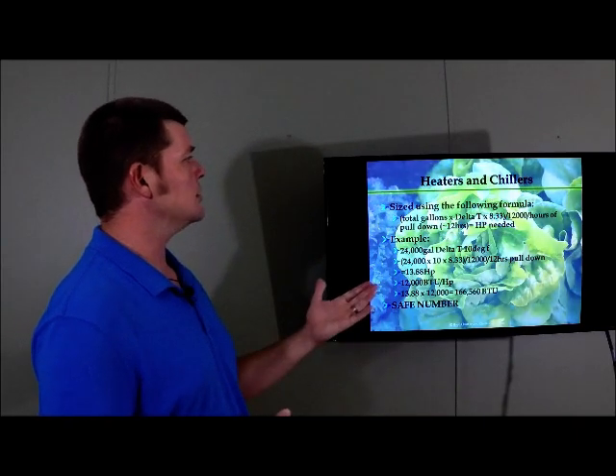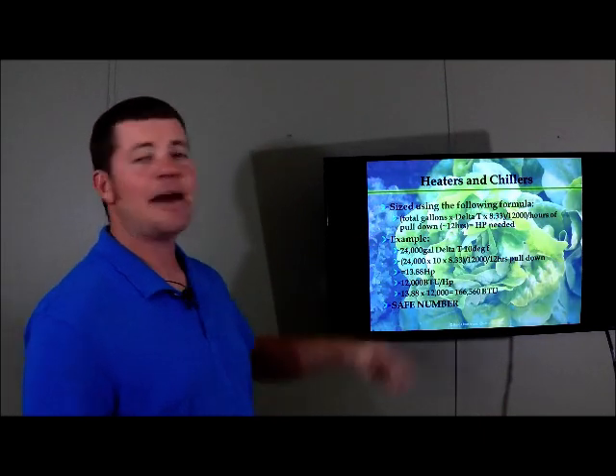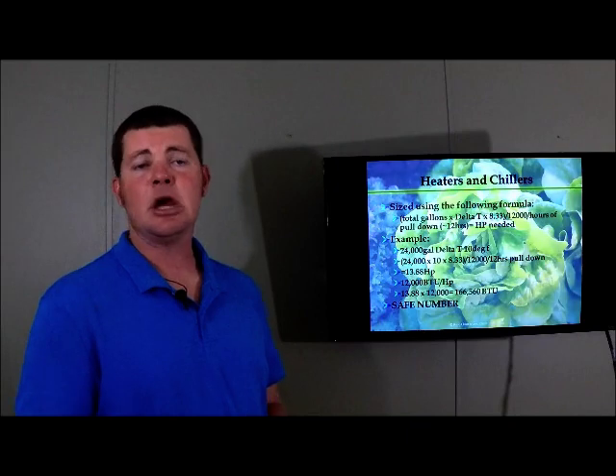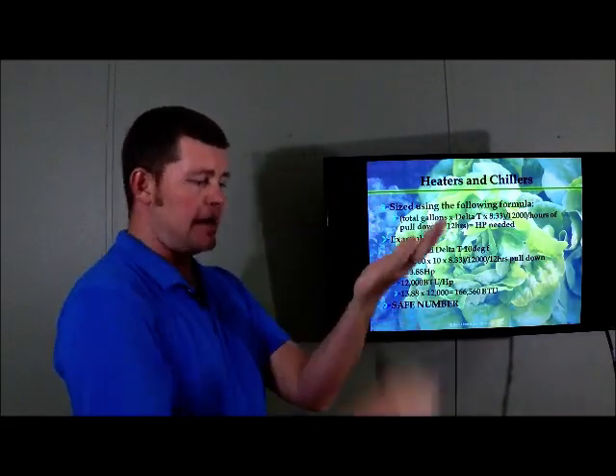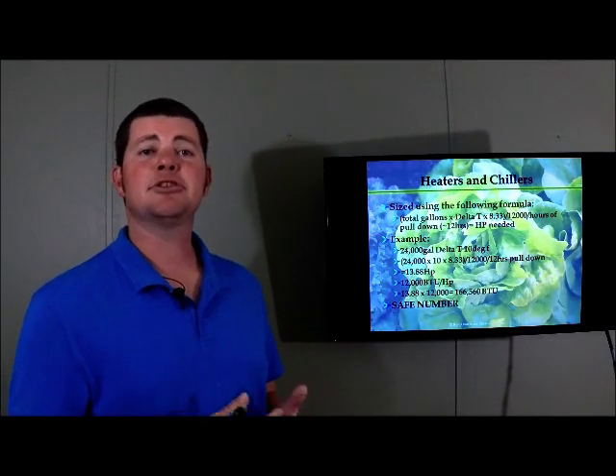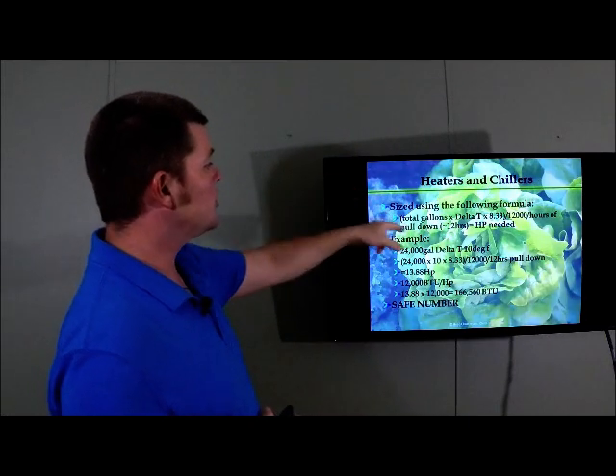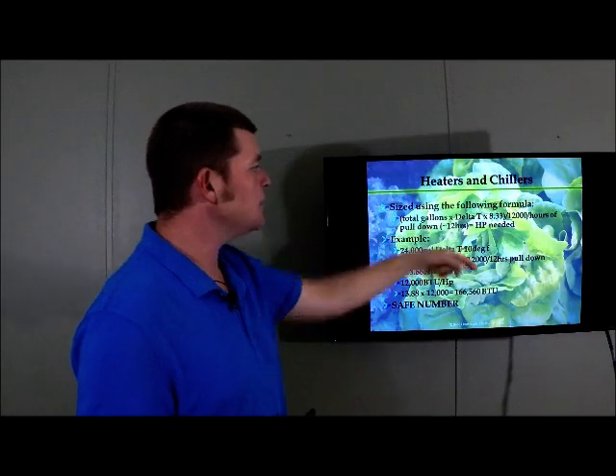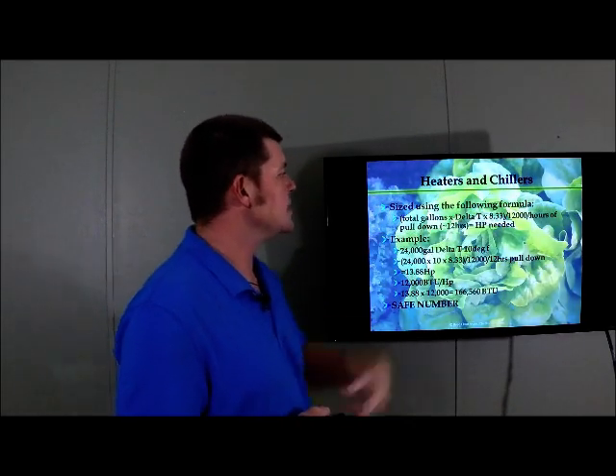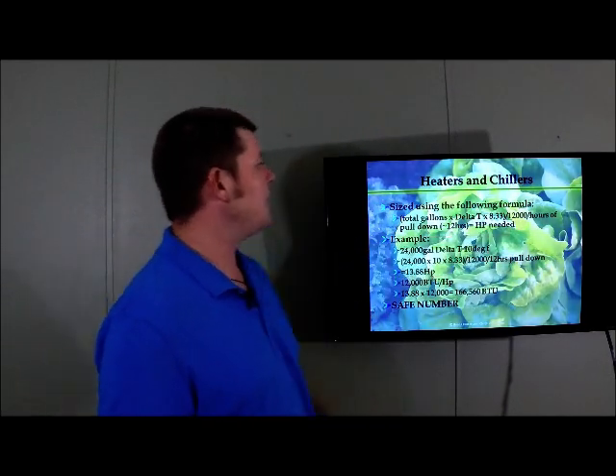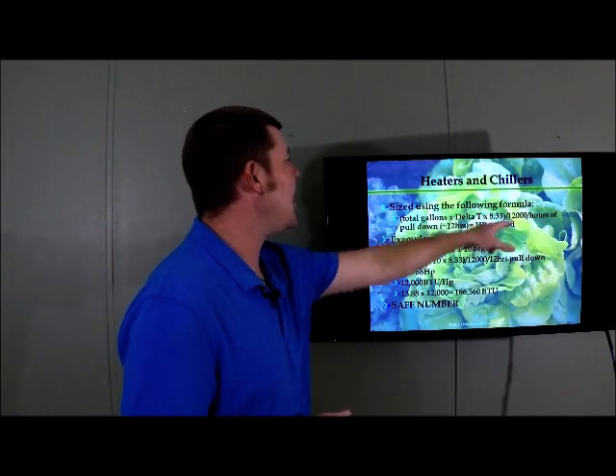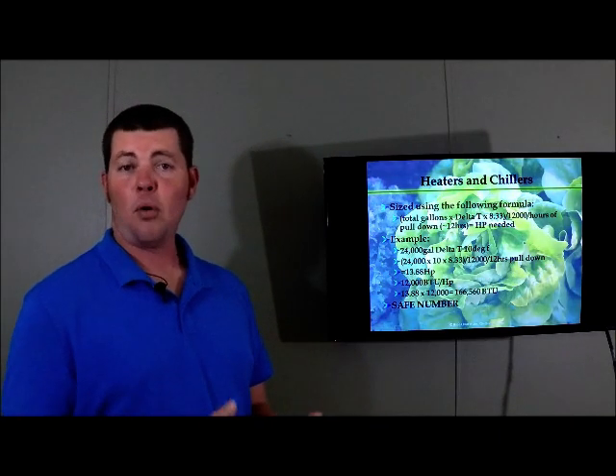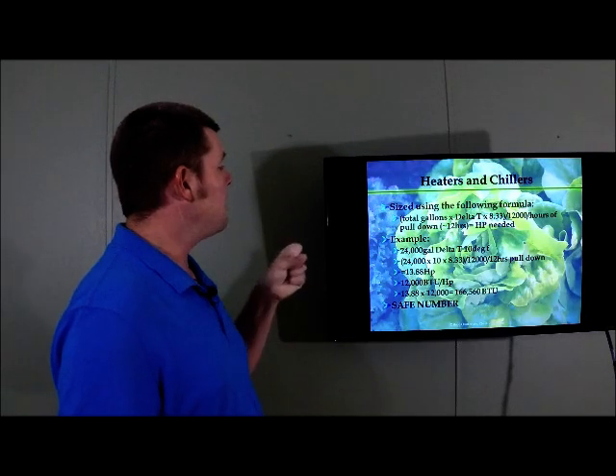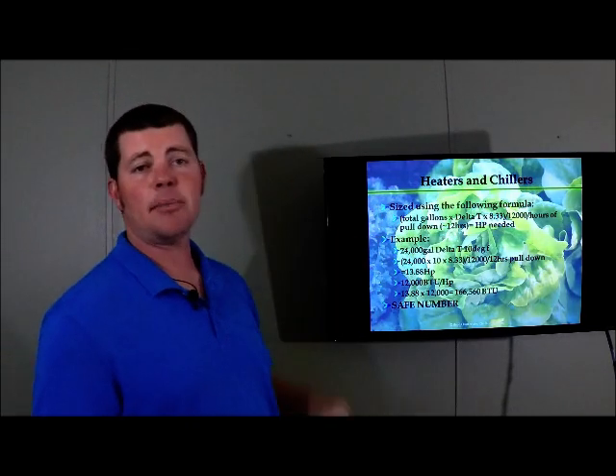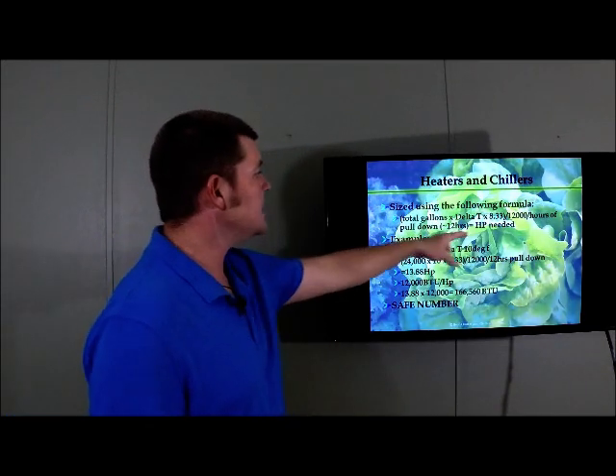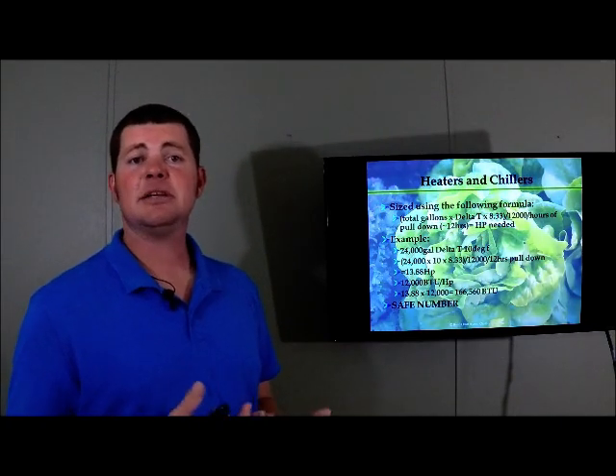So we're going to use the following formula to actually size the heater or the chiller. Heating, chilling doesn't matter. It's about delta T. That's the total temperature change you're trying to make occur. Delta T, whether it's 10 degrees up, 10 degrees down, 5 degrees up, whatever the temperature change you want, that's the delta T. So we use this formula. Total gallons that you want to chill times the delta T, which is your desired temperature change, times 8.33, that's a constant in the formula, divided by 12,000, another constant in the formula, and divided by how many hours you want to take to pull the temperature down, your desired change, okay? And right here I have in here 12 hours. That's the number I would use if you're sizing this chiller, 12 hours. And this equals how many horsepower of chiller or heater that you need to perform the desired function.